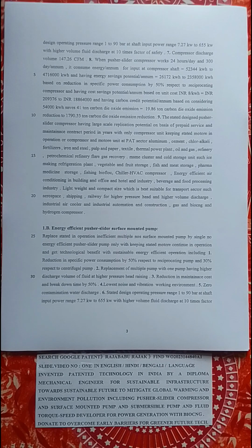Compressor discharge volume 147.26 CFM when the pusher slider compressor works 24 hours per day and 300 days per annum. It consumes energy per annum for input at the compressor shaft of 52344 kilowatt hour to 4716000 kilowatt hour, and has energy savings potential per annum of 26172 kilowatt hour to 2358000 kilowatt hour, based on reduction in specific power consumption by 50% with respect to the reciprocating compressor, and has cost saving potential per annum based on a unit cost of INR 8 per kilowatt hour.